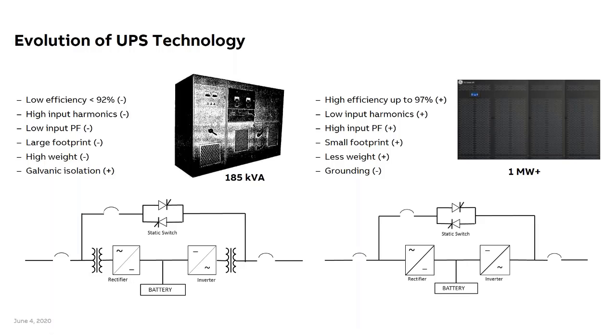Very big filters, big inductors, big capacitor filters to filter out the harmonics. There were two reasons for all the filtering and the transformers. One was to filter out the harmonics, as I mentioned. The other was that the first generations of semiconductors, the SCRs and the first transistors, had a fairly low voltage rating. So they could not operate at full line voltage. So in the UPS design, the transformer on the input would step the voltage down to something the SCRs or the transistors could safely operate at, and similarly on the output of the inverter, there would be a lower AC output from the inverter, but the transformer would step that up to 480. That was just out of necessity.